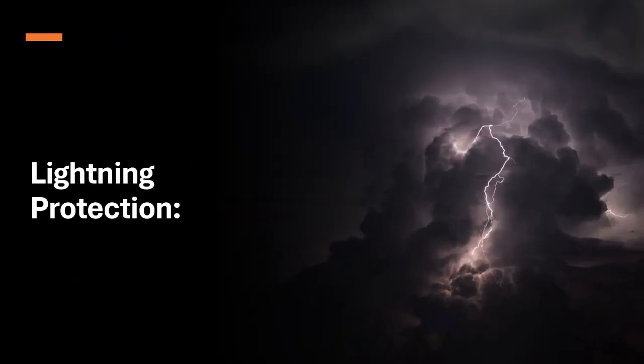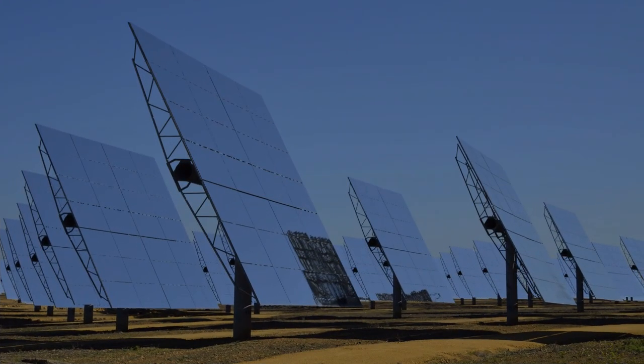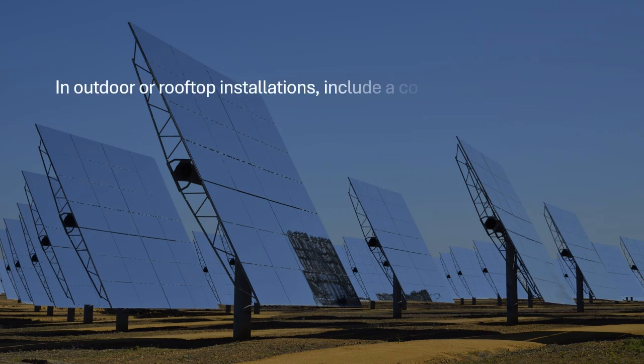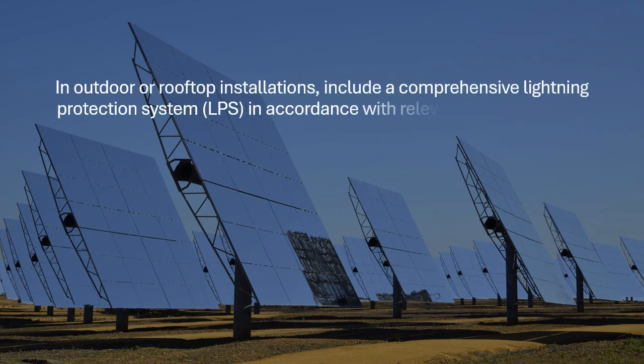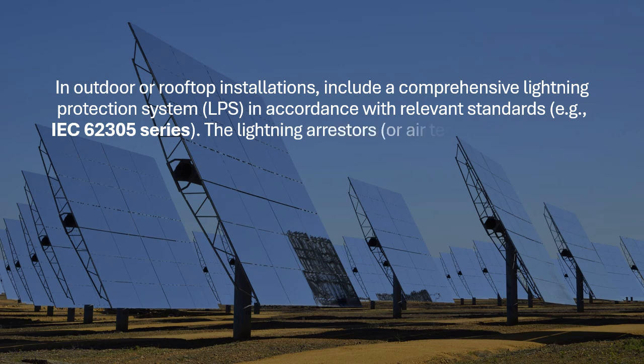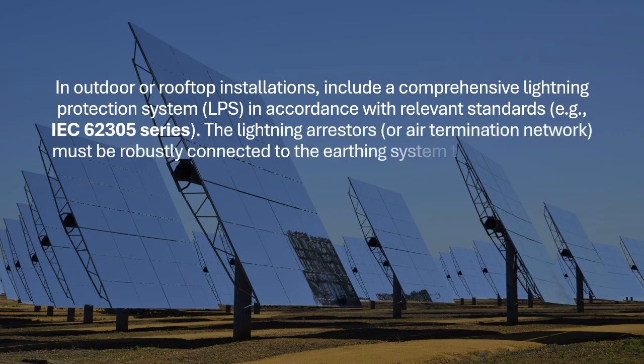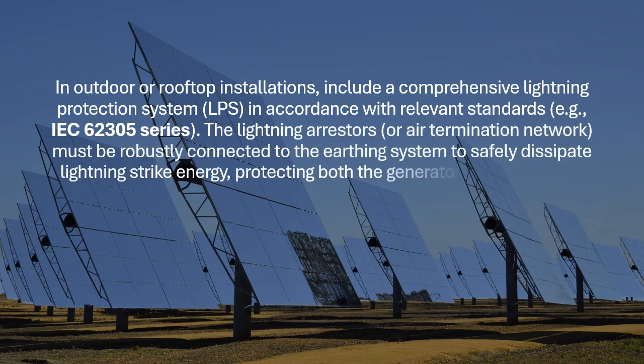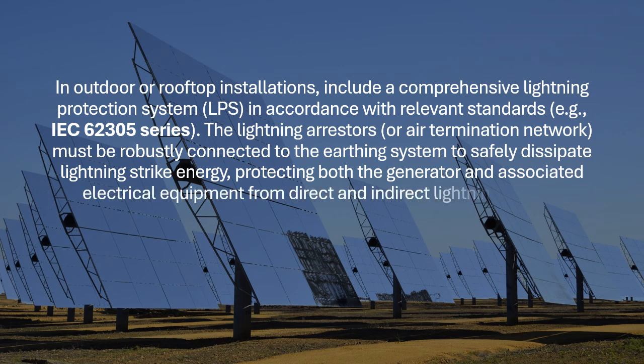Lightning protection. In outdoor or rooftop installations, include a comprehensive lightning protection system, LPS, in accordance with relevant standards, e.g., IEC 62305 series. The lightning arresters, or air termination network, must be robustly connected to the earthing system to safely dissipate lightning strike energy, protecting both the generator and associated electrical equipment from direct and indirect lightning effects.